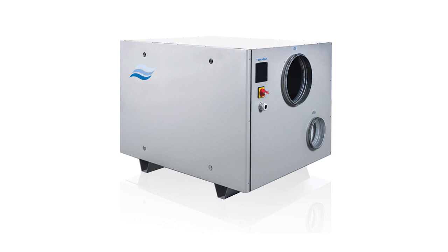Well, the energy needed to operate a desiccant unit is used mainly to heat the regeneration airflow, and the temperature of that airflow needs to be somewhere between 90 to maybe as high as 120 degrees C. That is hot. How is that heat produced? Well, normally with an electric heater, but if there is waste heat available from another process on site, this can be used with a heat exchanger to preheat the regen airstream and reduce the energy burden.